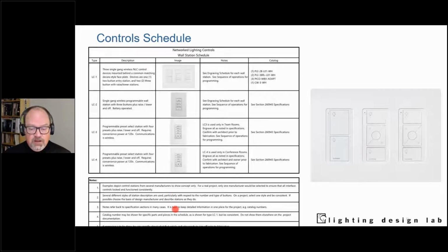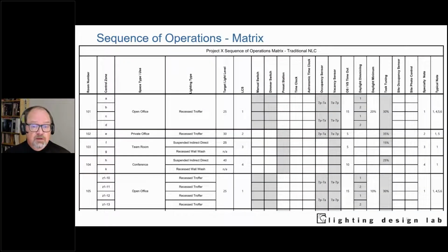Now, to take that into the sequence of operations, it might look something like this. We have room 101, zones A, B, C, and D. They're in the open office, all recessed troffers. My target light level is 25 foot-candles. My lighting control station type is 1. I'm going to have a manual switch in there, and a dimmer switch in there.